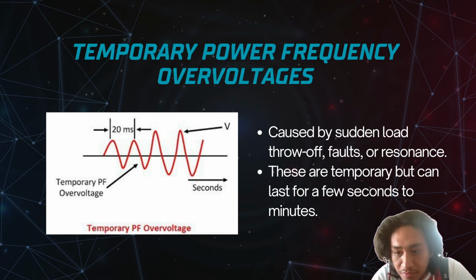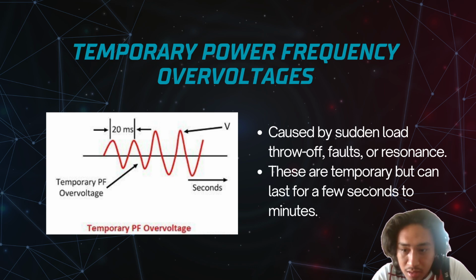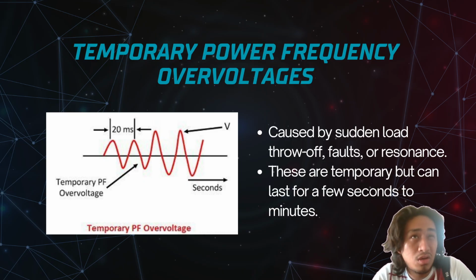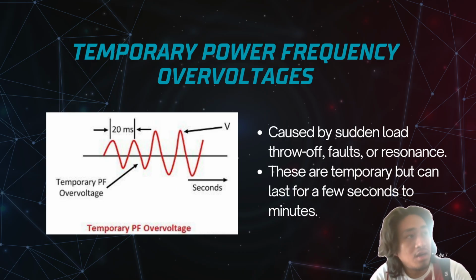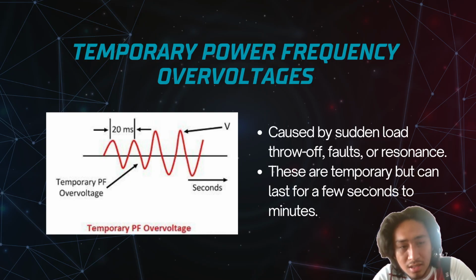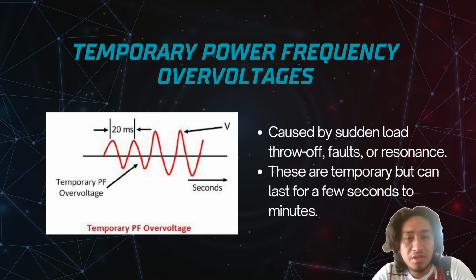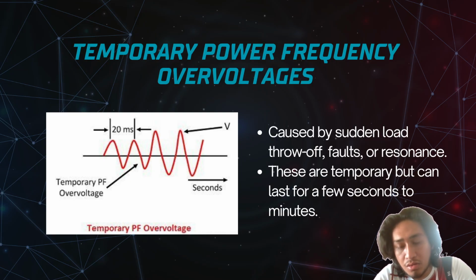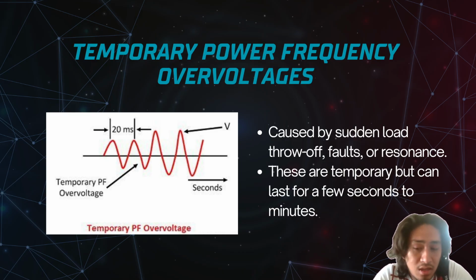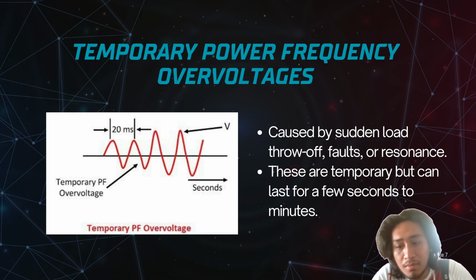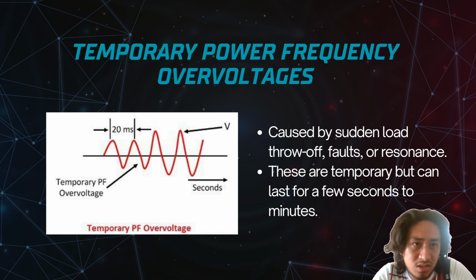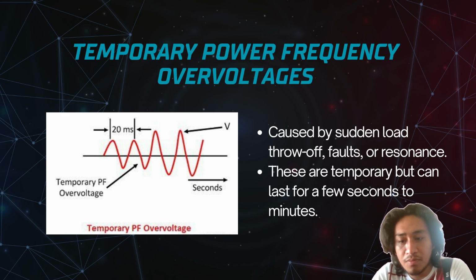As you can see in the graph, there is a voltage spike at a certain time, and this phenomenon lasts longer compared to transient overvoltages, since transient overvoltages only occur for a few milliseconds. So this is caused by sudden load throw-offs, faults, or resonance.